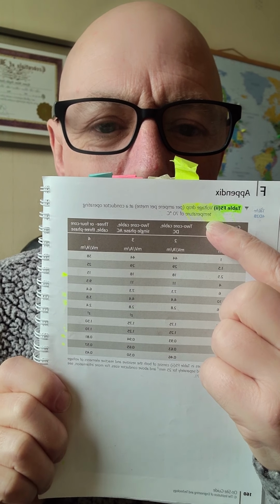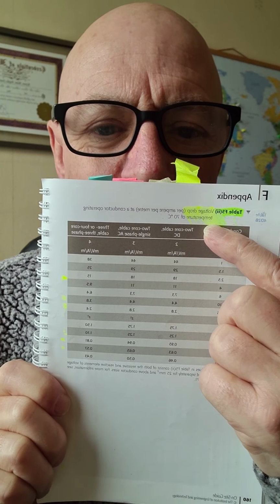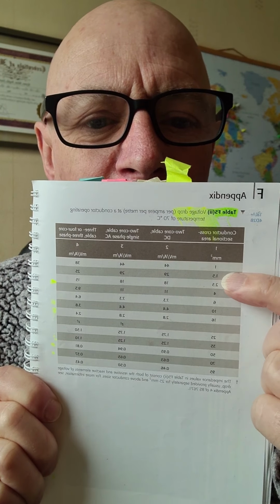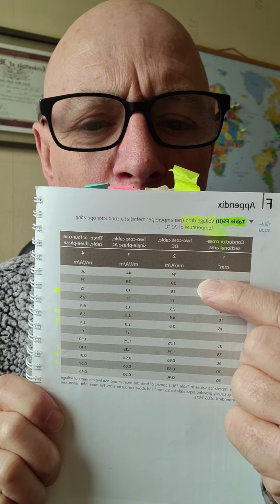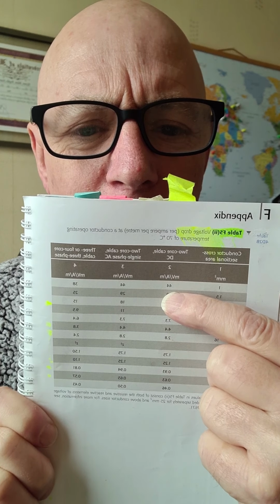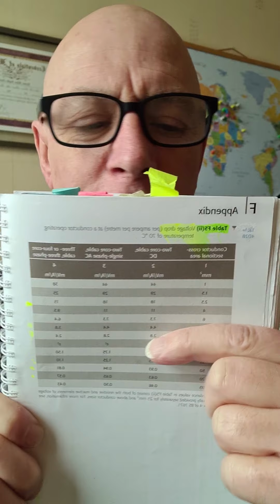So that's table F5.1 for multi-core cables, and that's generally round cables. Next up, we've got table F5.2, okay, and that's to find the voltage drop for multi-core cables. It's quite a simple table to use. You just look at the size of cable you've got, check whether it's 2-core or so on and so forth, and then you find your millivolts per amp per meter. So that's quite easy to use as well, and that's the one you'd use in your calculation for voltage drop.